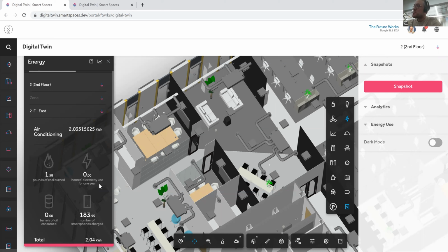So what we did was remove all those 14 connections and get a single secure connection brought into the building. We rationalized these networks. Typically in one of these buildings, you're going to have an access control and CCTV network, a BMS network, and a lighting control network. We want to segregate those, secure those, and then link those to our system. And that's when we're able to extract the data.